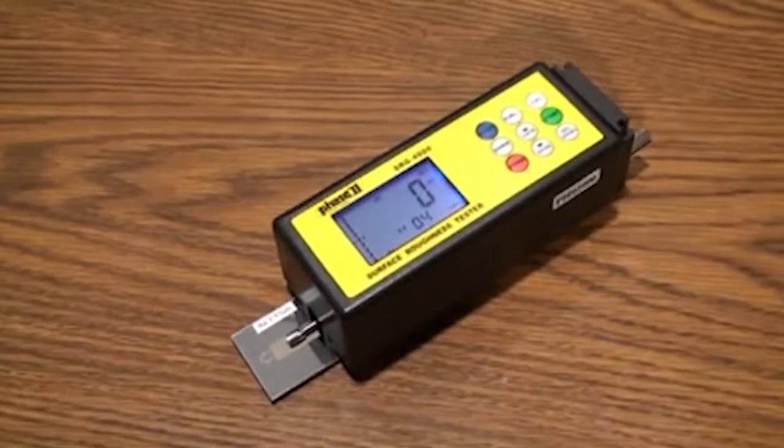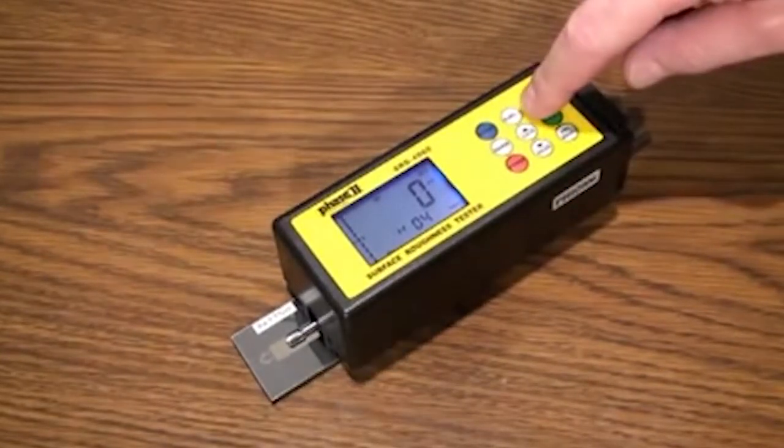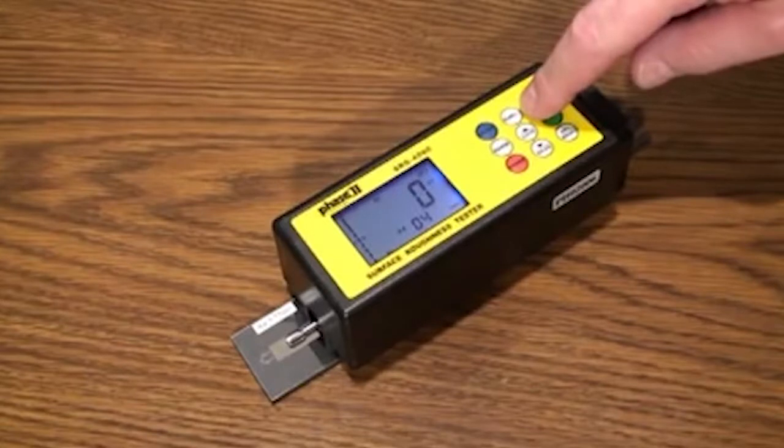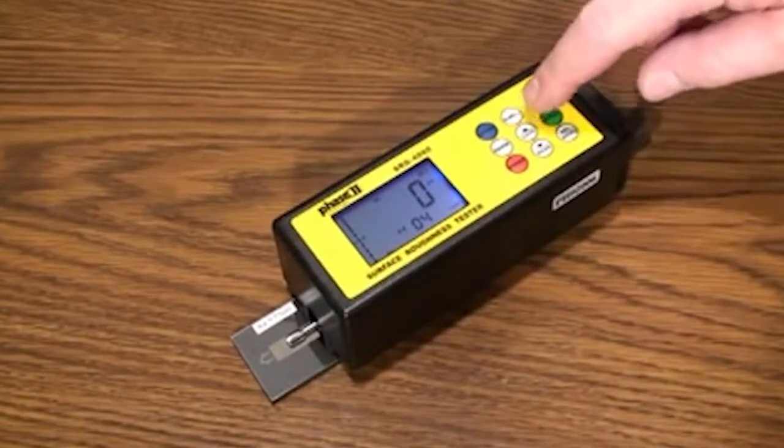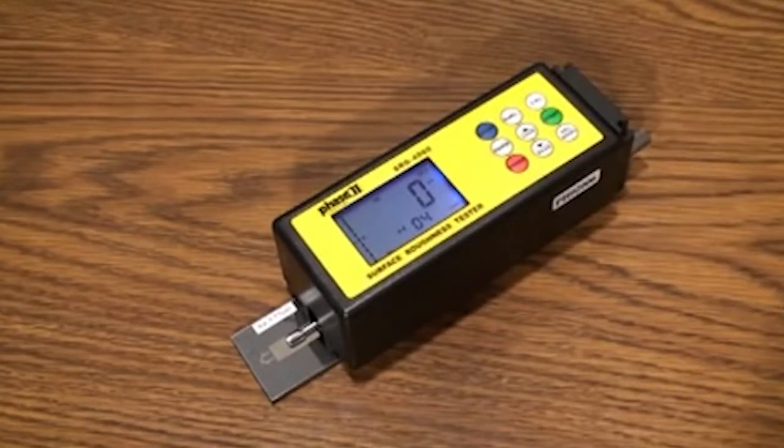The RA, RZ button determines the surface roughness parameter. The parameters are determined by your requirement, usually on a drawing or standard. If no parameter is called out, RA is commonly defaulted, the most popular being RA.